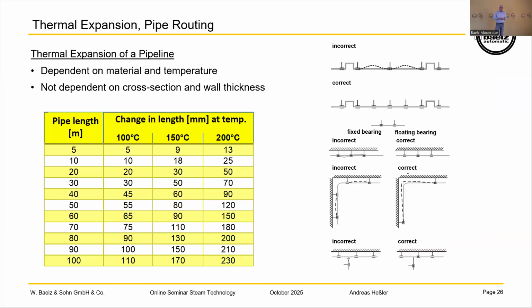Thermal expansion of pipelines. A very, very long theme to talk about normally. Just for your information, the extension depends on the material and the temperature, and not on the cross section and the wall thickness. So be sure you check that table so that you make your bearings and your holdings exactly correctly. The piping manufacturers will also say something about that when you have to bear and hold the pipe. I show you on the right side some examples of how to protect or correctly mount the bearings. You can have a look at that.